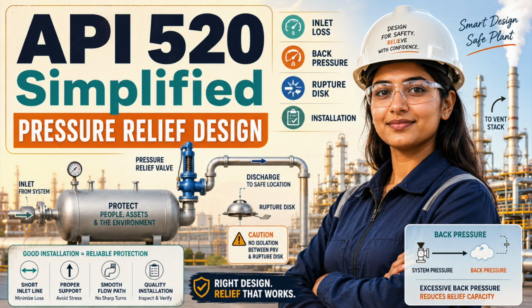Pilot-operated valves offer another set of advantages. They can operate closer to set pressure, reduce leakage, handle large capacities, tolerate certain back pressure conditions, and use remote sensing. They can also fail when the service is dirty, viscous, corrosive, polymerizing, freezing, or loaded with solids. Small pilot passages, sensing lines, seals, and control components can be vulnerable to plugging, hydrate formation, wax, contamination, and material incompatibility. More sophisticated does not automatically mean more reliable. Complexity must earn its place in the design.